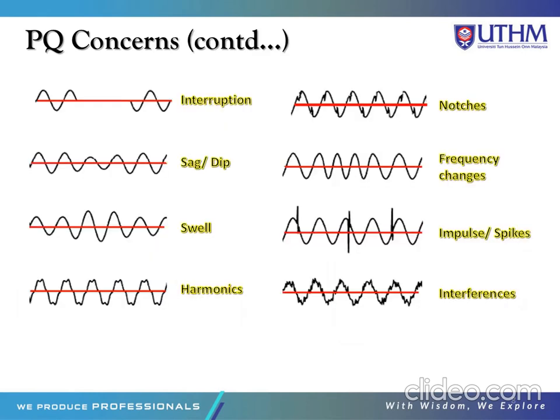This is the PQ waveform. The first one is the interruption, which is a break in the signal for a certain period. Next, voltage sagging or dip, where the value of the voltage dips for a certain period. Then voltage swell, where the value is increased for a certain period. And this is the harmonics. Usually the harmonics is taken at the peak of the value.